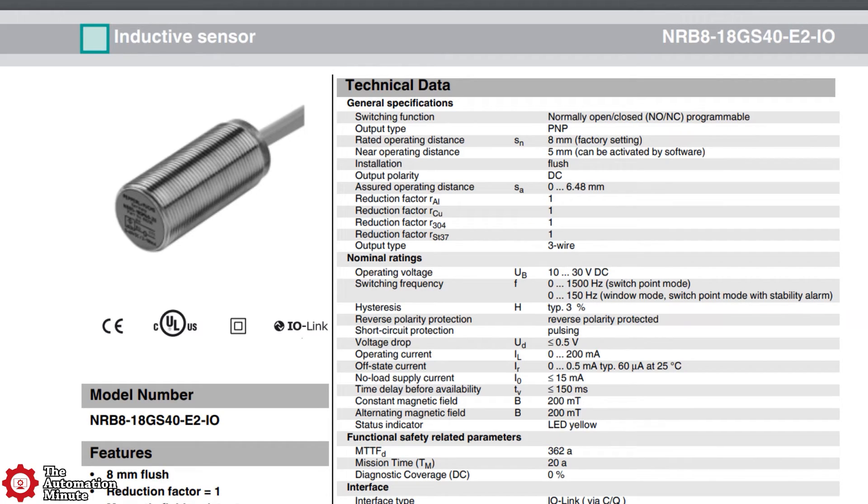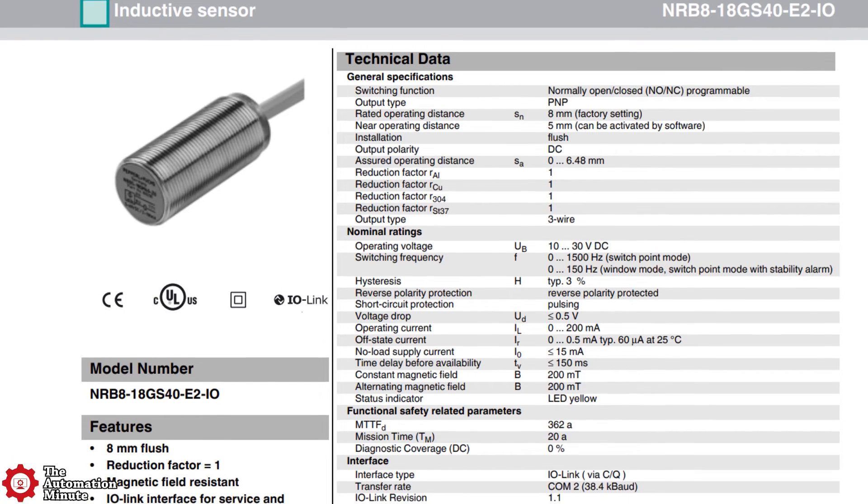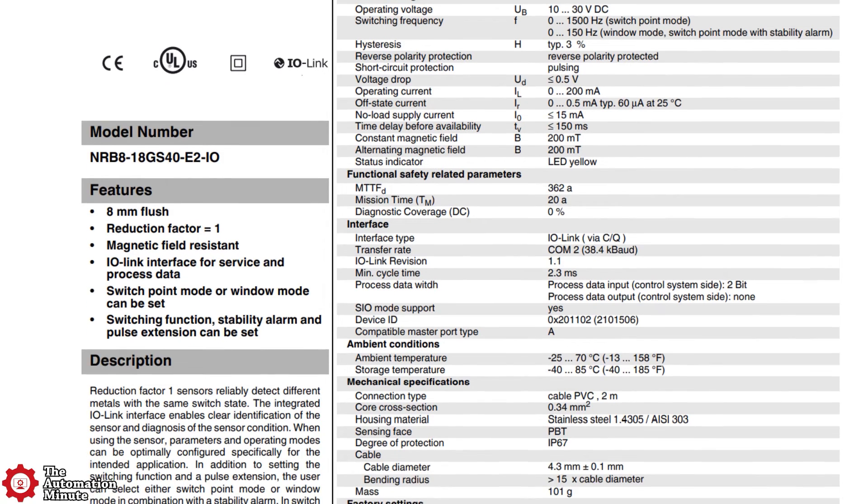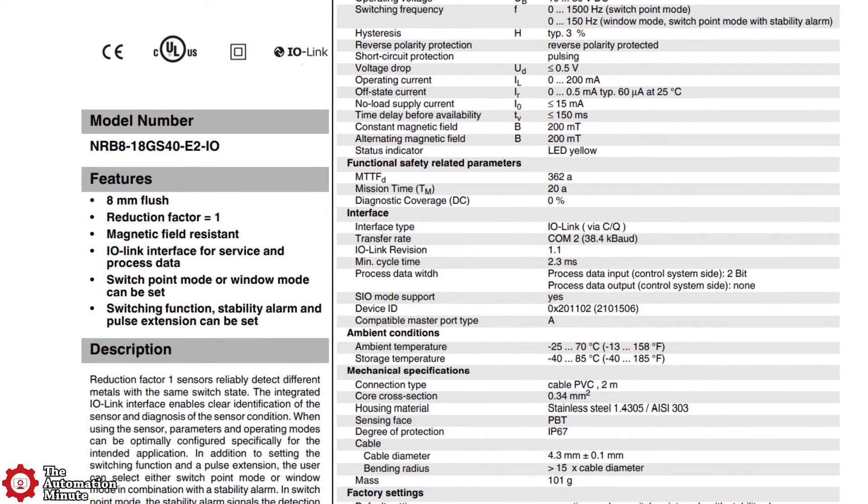The prox itself has a factory-set operating range of 8mm and an operating voltage range of 10-30V DC. Its housing is made of stainless steel, and it's rated for IP67, and a temperature range of minus 25 to 70C.